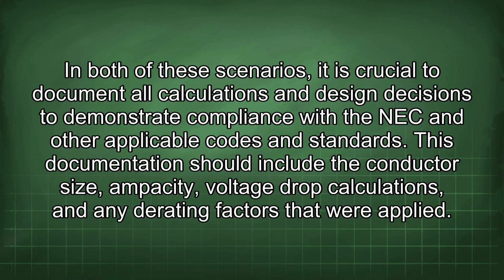In both of these scenarios, it is crucial to document all calculations and design decisions to demonstrate compliance with the NEC and other applicable codes and standards. This documentation should include the conductor size, ampacity, voltage drop calculations, and any derating factors that were applied.